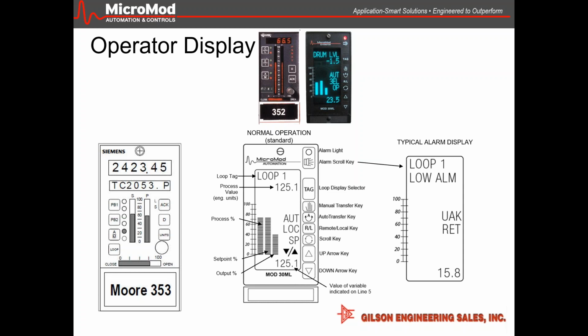What you're looking at, on the MicroMod display where it says drum level, is actually a 3-element drum pack. You can tell because just below it, where it says AUT for auto, it says 3-element. If it were set up as a true 3-element, as steam flow lessens over time, it would drop back to a single element at some break point, transitioning from 3EL to 1EL. You can change where that switchover happens from the front face, in the tuning page, but it's behind a password, so it's very protected.